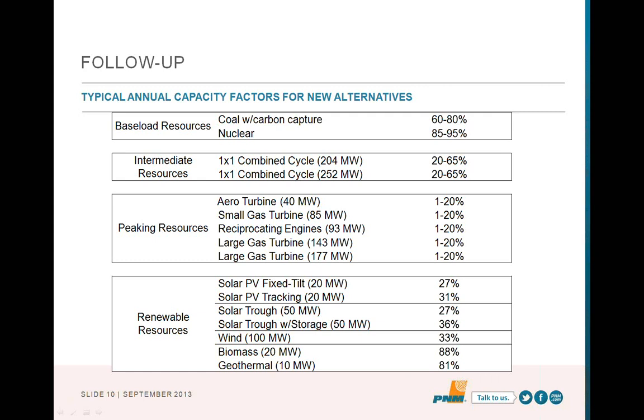Yes, sir, Rob? Just that I've been familiar with a lot of wind energy testing throughout the state at optimal locations, including on the PNM system, and I'm just wondering if the capacity factors are accounting for the optimal locations. I mean, we're getting numbers like 40 to 50% net capacity factor with current technology, like GE 1.7s or what have you. If technology is improving, those locations that we're assuming for capacity factor, well, I would imagine should be optimal locations, but there's enough of them here in New Mexico.